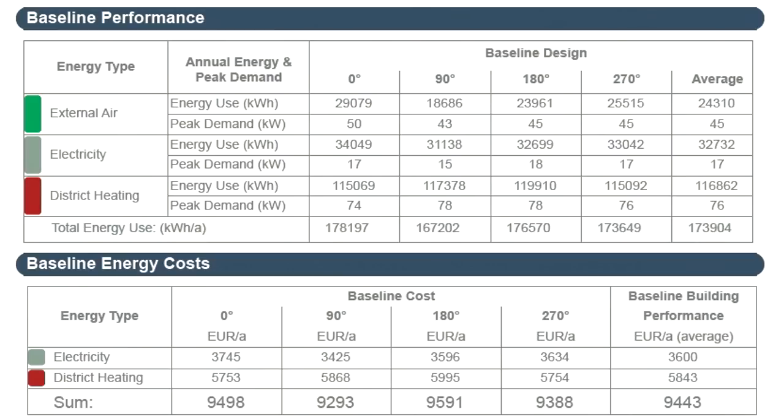According to ASHRAE, the baseline building performance data generated this way represents the average design solution better because it disregards differences in orientation caused by specific architectural solutions. EcoDesigner STAR's automatic baseline building processing functionality is also a great tool for checking whether the designed building's orientation is truly optimized, or perhaps a rotated layout would be more energy efficient. On the other hand, automatic ASHRAE 90.1 processing requires five simulations — the designed building plus four baseline building versions — versus the single unrotated baseline building method that only requires two simulations. The runtime of a performance rating analysis using the single baseline building method is therefore much shorter.